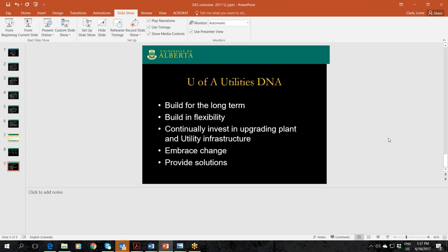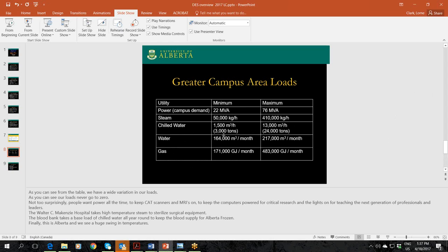I think it's got about 5 tons. No, it must be more than that. I think our cooling load is around 3,000 tons off this basin, and it's good for about 6 or 8 hours. I'm not a mechanical person, so I don't understand it as well as I should. It's about 5,000 tons off the top of my head. I know it contributes overall, but it certainly wouldn't be enough on its own. I think it might be enough on its own at our minimum load, but certainly not at our maximum load. The thought was that it would help run during the day to control the demand and then recharge at night with the demand charge being low. Exactly.